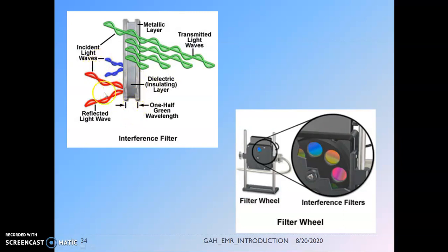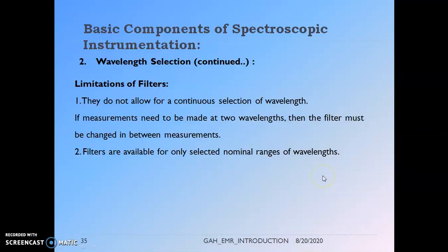The limitations of filters: they do not allow for continuous selection of wavelength. If measurements need to be made at two wavelengths, the filter must be changed between measurements. We cannot take one filter and work over a wide wavelength region — filters are available only for selected nominal ranges of wavelength and cannot be used over the entire wavelength region.